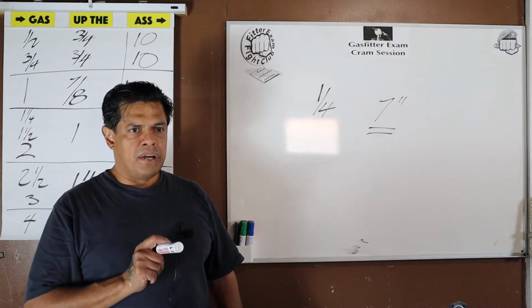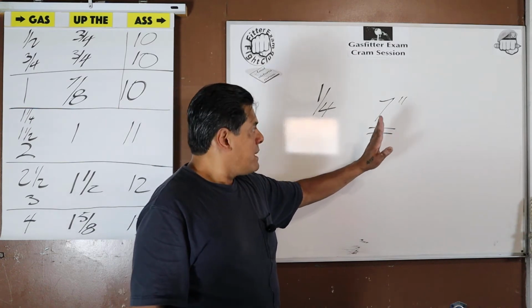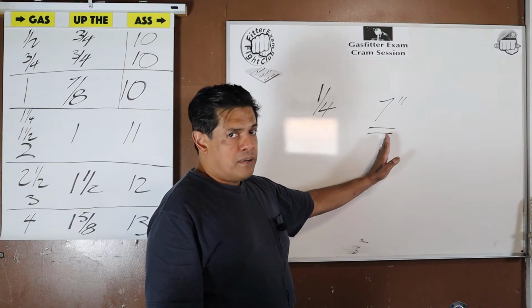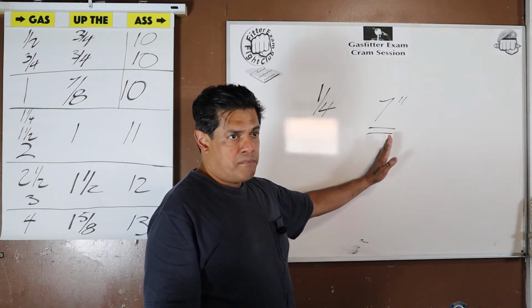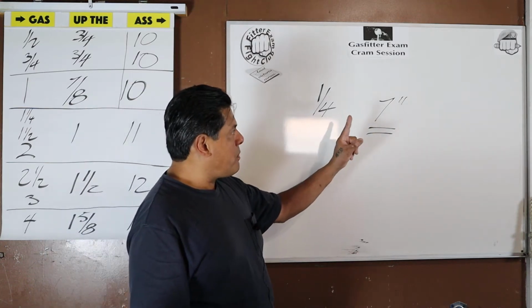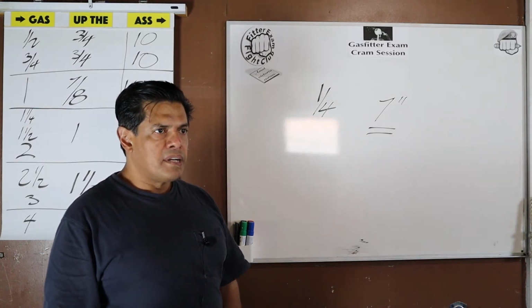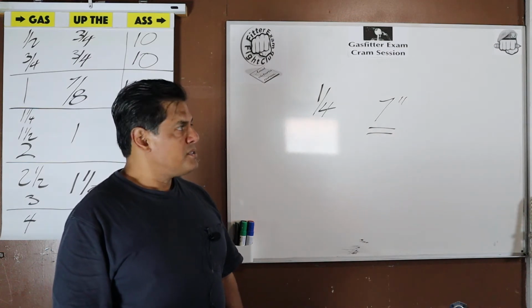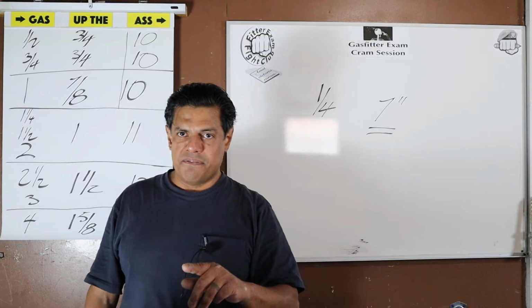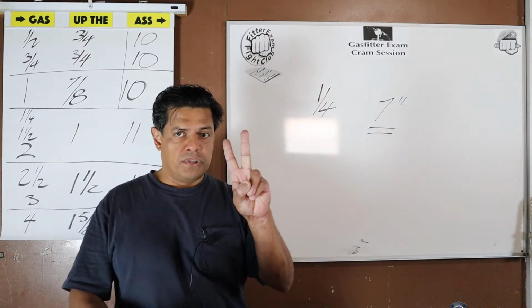But I'm glad you tried to corner me on it, because it now reinforces something else that's still good for us. This 7 and this 1/4 are doing work for us, because here's the 7 that appears in an area that we weren't going to see a 7. Okay, technically it's not in the code, so I'm still right. But more importantly, 1/4. Maybe you're saying, 7 inches of the manometer, I got to remember it's 1/4 of a PSI. Well, it's not that hard to remember now, because now when you hear 1/4, not only is it a 7-inch column of water, it is also the pitch within 15 feet to prevent traps in a wet gas system. So 1/4 does 2 jobs for us.